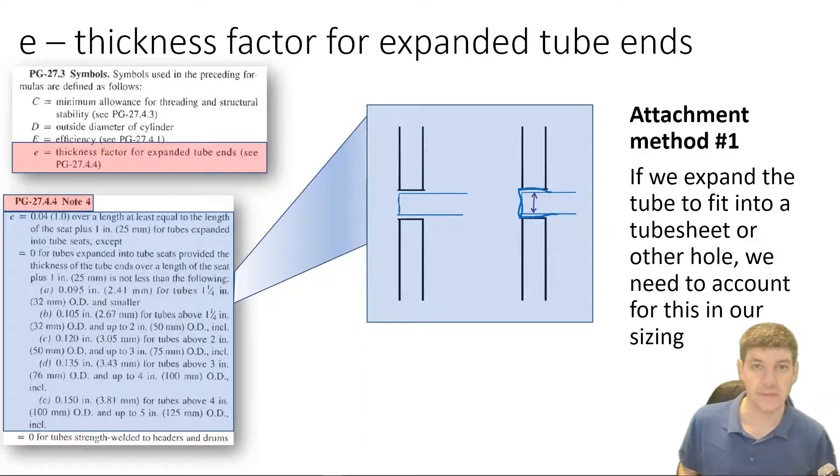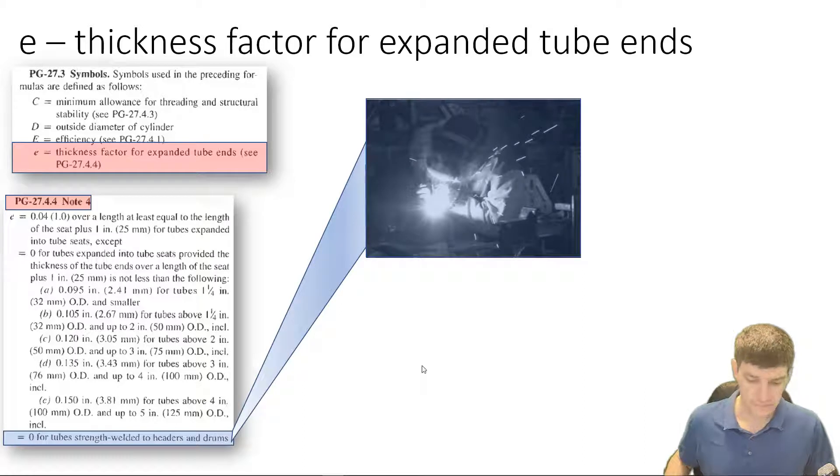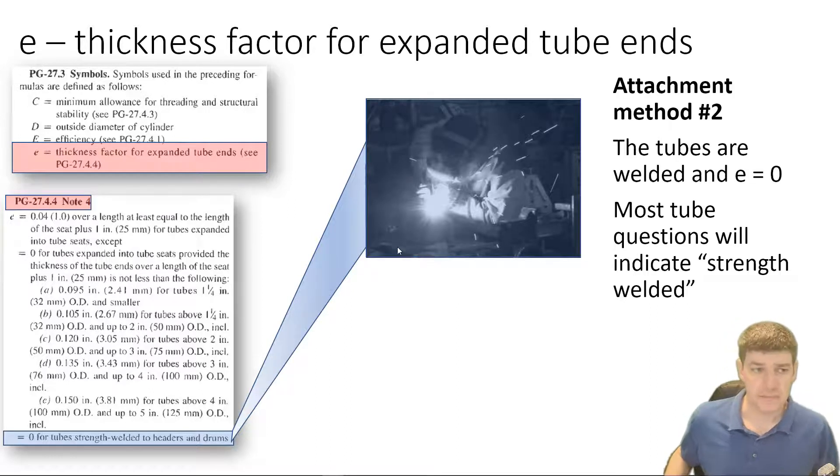The last statement in this section talks about our next attachment method. And our next attachment method is when we weld tubes. So, the tube's attachment is by what's known as strength welding, or welded attachment to the header, or the drum, or wherever we're attaching it to. And in this case, E, we don't add any extra thickness because we don't weaken the tube. And most of your questions are going to indicate strength welded as the connection. So, this is the most typical application of this.